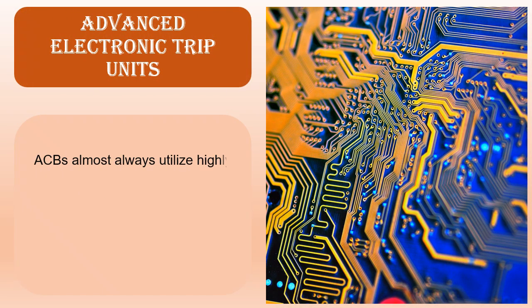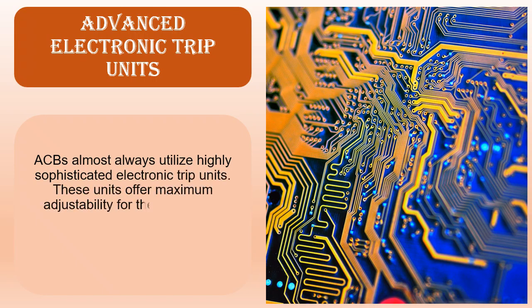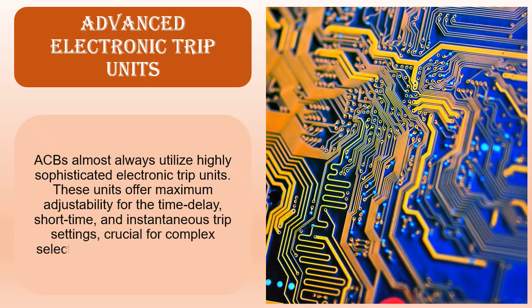Advanced electronic trip units. ACBs almost always utilize highly sophisticated electronic trip units. These units offer maximum adjustability for the time delay, short time, and instantaneous trip settings, crucial for complex selective coordination strategies.